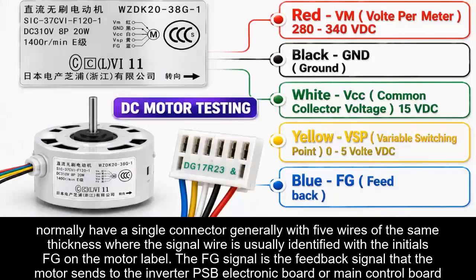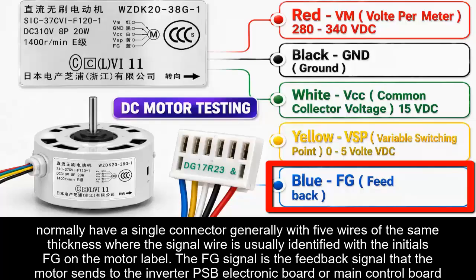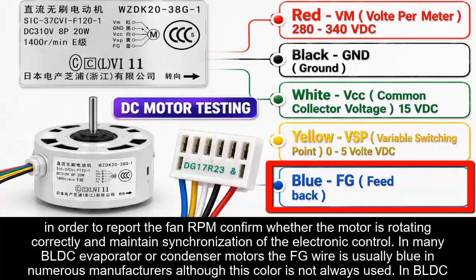The FG signal is the feedback signal that the motor sends to the inverter PCB electronic board or main control board in order to report the fan RPM, confirm whether the motor is rotating correctly, and maintain synchronization of the electronic control.